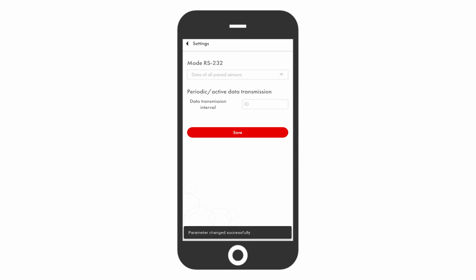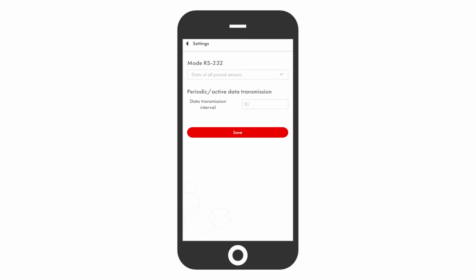The last option enables the base to transmit all the data of all the sensors paired with the base in ASCII strings. If this option is selected, more pairs of parameters can be transmitted per each sensor. You only need to activate them in the RS-232 settings of each cell of the base with the sensor connected to it. The order of the parameters of each sensor in the string depends on the number of the sensor's cell on the list in the menu of the base. You can also configure the interval at which the base will be transmitting the sensor's data to the tracker. Put the value in seconds that you need and then press the button to apply and save the changes. For example, if you put 30 seconds, the base will be sending the data received from the sensor or sensors to the tracker every 30 seconds.